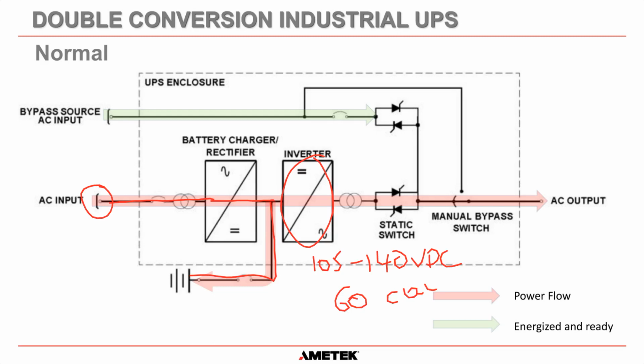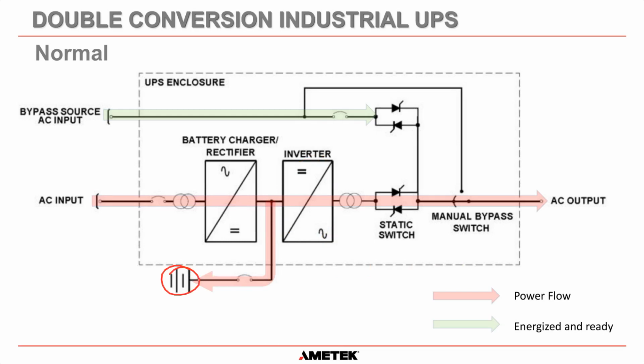But in truth, AMETEK SCI could make an inverter that operated off 50 volts if they wanted to. But for our UPSs, this is the realms that we usually stay between. The batteries are charged at what the batteries require. So most lead acid batteries say that it should be 2.25 volts per cell. And if you multiply that by 60, the float voltage will be 135 volts DC. So that is why the DC bus is 135 volts. Okay, it's the only reason why, because the 60 cell lead acid battery is the most common in industrial applications.